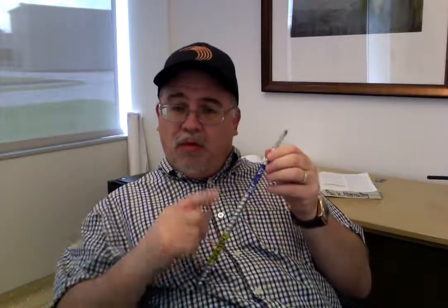But let's talk about your traditional MC cable. And this one, I know we remember that this is blue, so this is a steel armored MC cable. Now what if I want to install this in a wet location? Can I do it? Even though I know the conductors inside of here are rated for wet location. They're probably going to be a THHN/THWN-2 or an XHHW-2 depending on the product you buy. Yeah, the conductors are rated for wet location, but the armor itself is not, and it wasn't evaluated for it. So that's where your problem is.